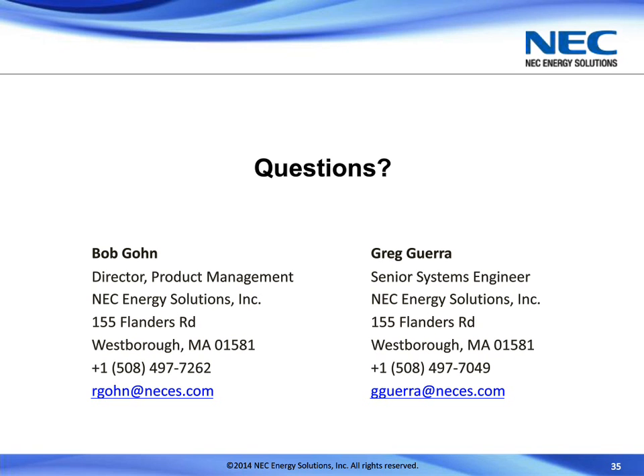Well, one thing that we both definitely mentioned that I would like to mention as a key takeaway is really the usable energy. You really need to understand how to make a fair comparison there. It starts with a derating due to discharge rate, derating due to temperature, allowable depth of discharge, and that gets you your apples to apples cost on day one. And then after that, it's the service life, which really gets you your total cost of ownership. So you need to have that kind of calculation in mind when you choose your system.